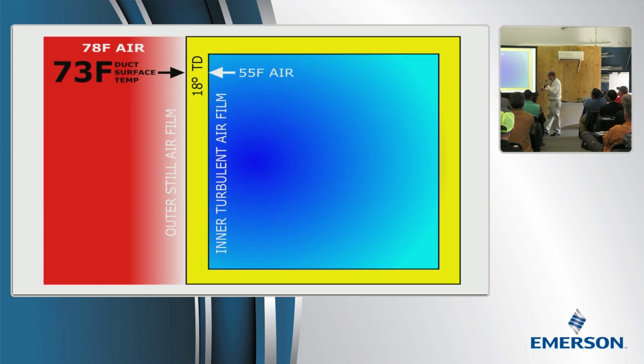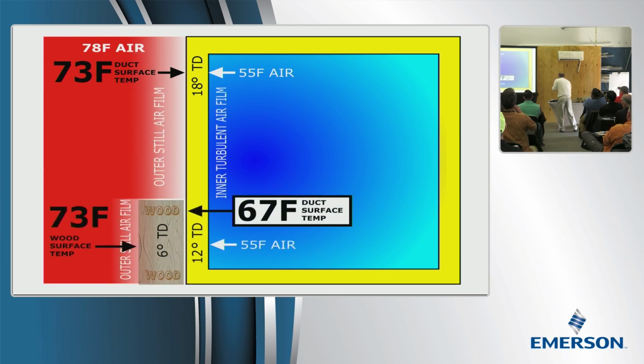Now, you remember that I said that ducts don't sweat when it's over 90. So here we got a 73 degree surface, right on the edge of wetness, 73 degrees, 55 degree air on the inside. We got an 18 degree temperature difference across the wall of the duct. Everything's going good, and then we do that. And that is going to be a problem. As soon as we put this up against this, it's going to get wet. It needs a gap.